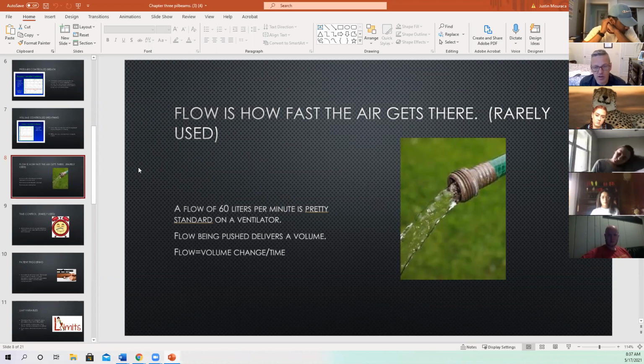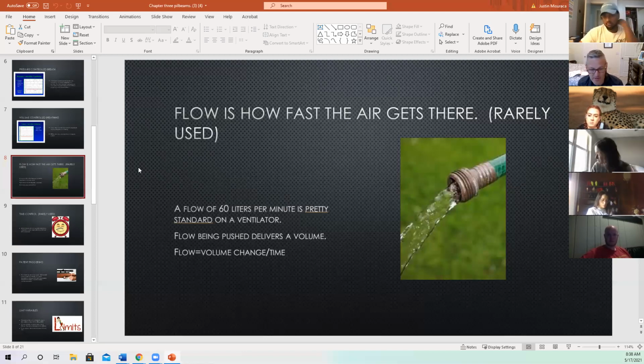We started doing flows. When we deliver flow to a patient to generate a breath, we typically do it at 60 liters a minute. Do you know why 60 liters a minute? Is it patient related or is it us related? Because we used to have to calculate absolutely everything by hand, right? So you would do a 1 second I time and 60 liters of flow per minute. So 60 liters of flow per minute equals 1 liter per second. And if you have 1 liter per second and a 0.6 second I time, you're getting a tidal volume of 1000, right? So it makes the math really easy, right?